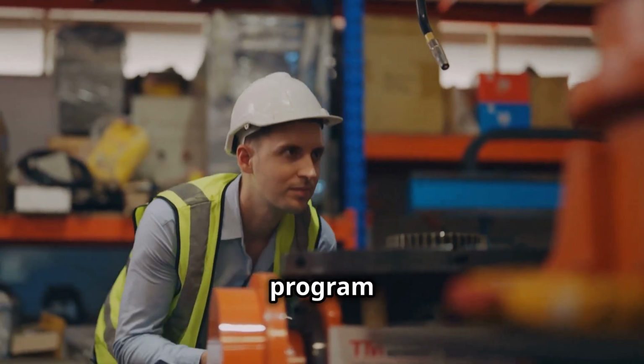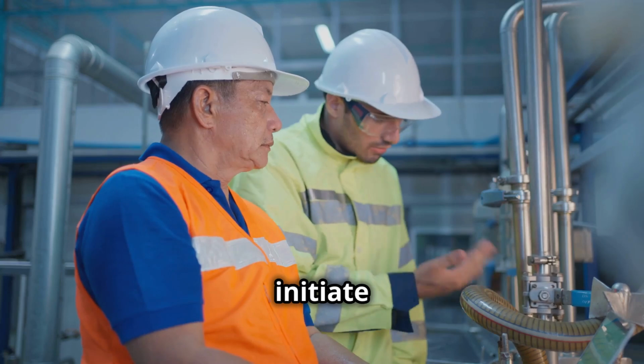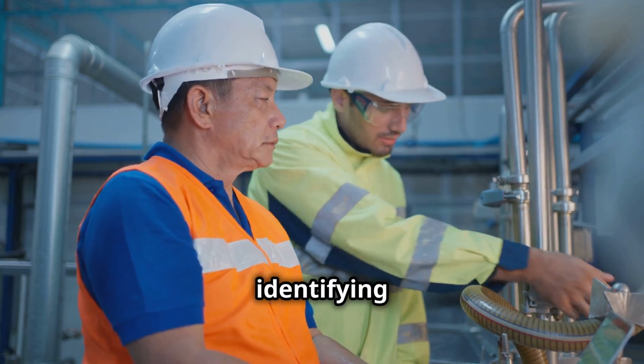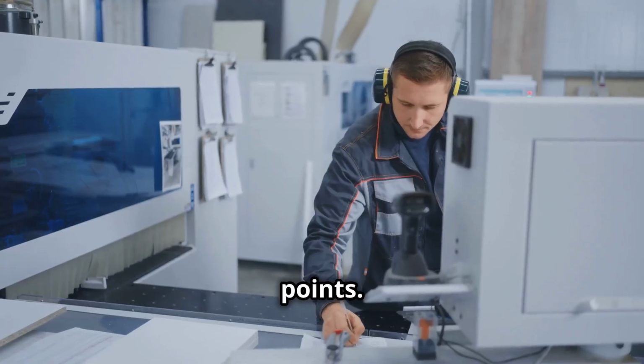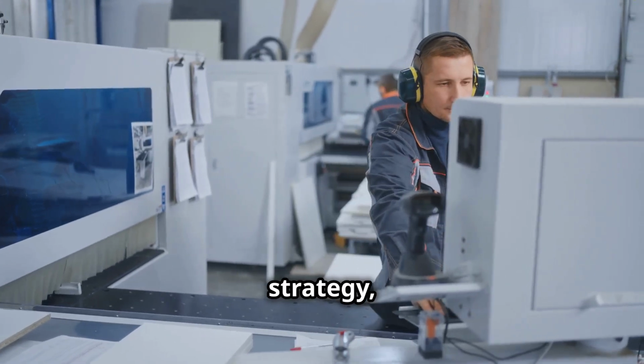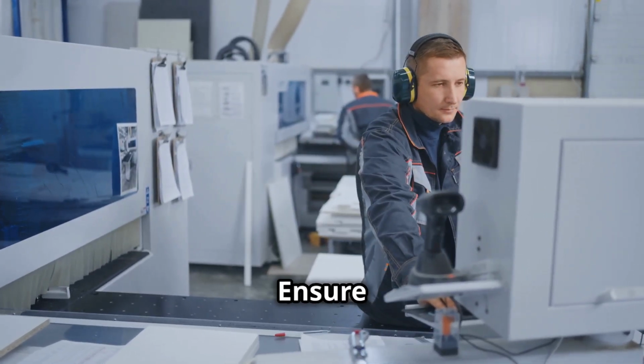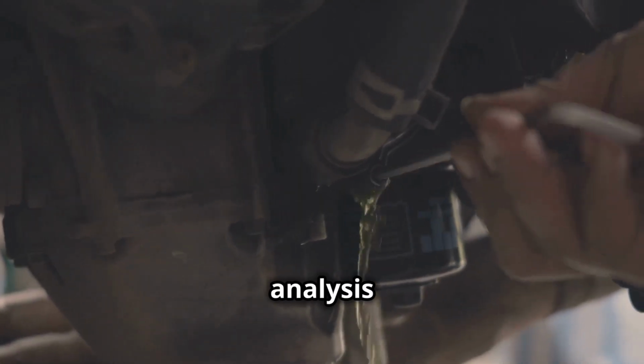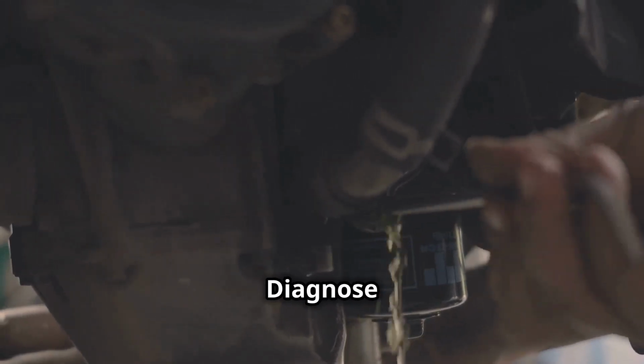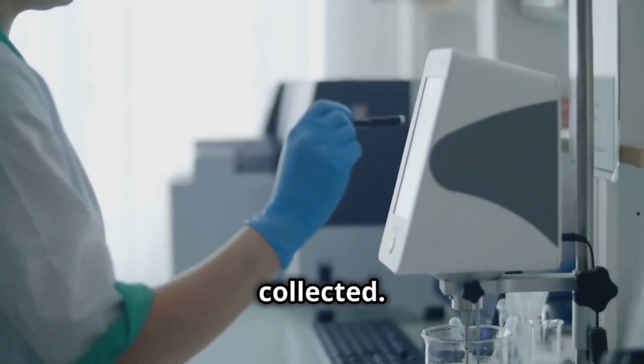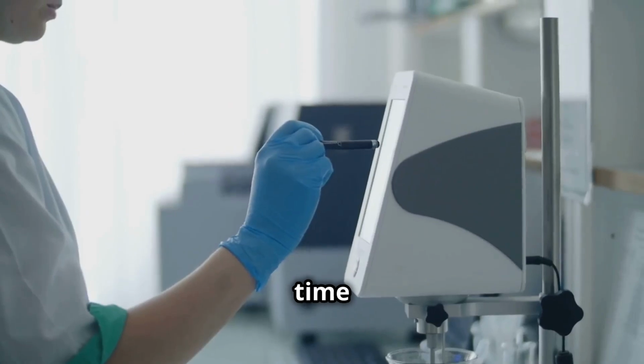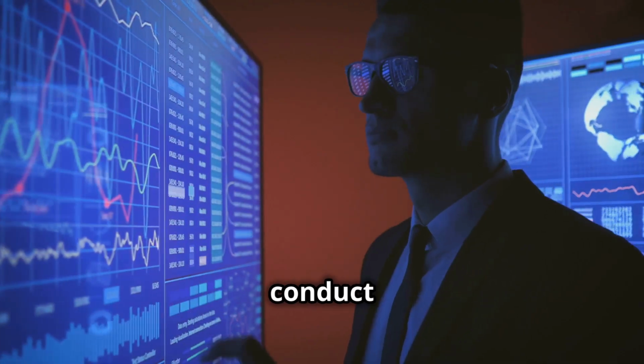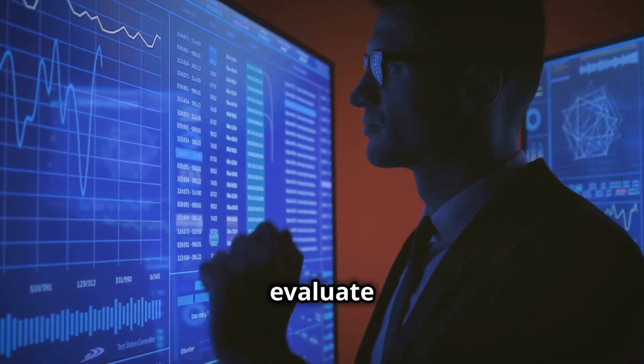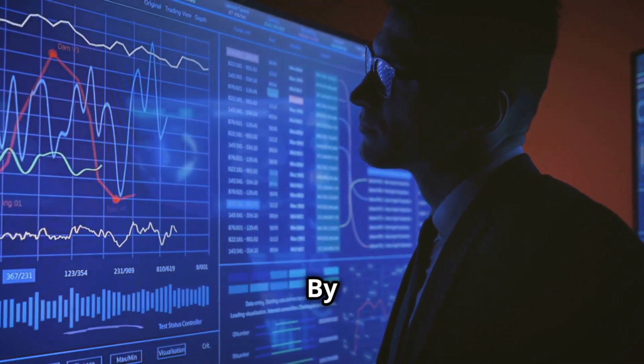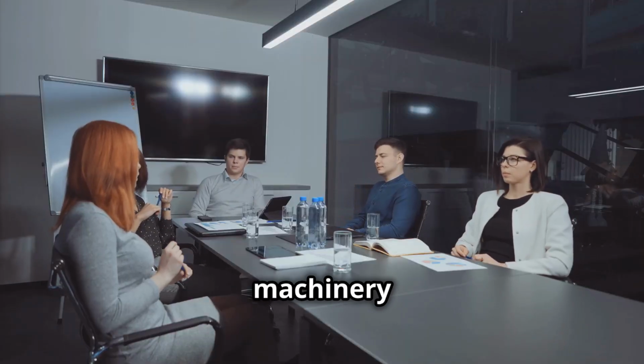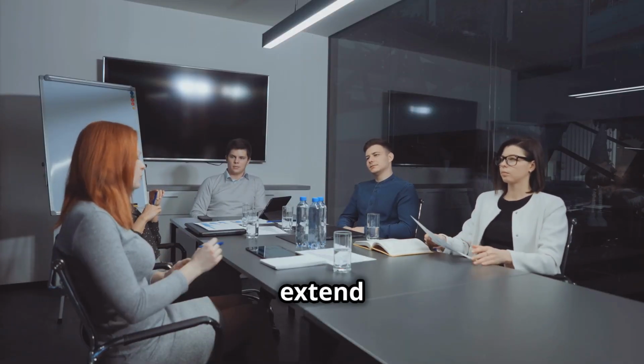Oil analysis program design steps. First, initiate the program setup by identifying machinery and lubrication points. Next, develop a sampling strategy, including frequency and methods. Ensure proper data logging and sample analysis procedures are in place. Diagnose and prognose based on the data collected. Track performance over time to identify trends. Finally, conduct a cost-benefit analysis to evaluate the program's effectiveness. By following these steps, you can optimize machinery lubrication and extend equipment life.